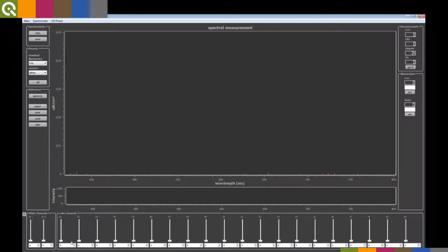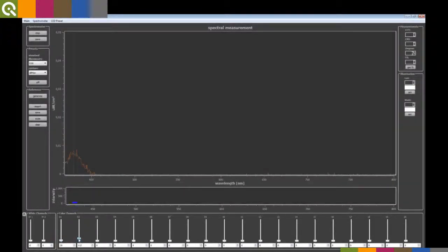One way to get the Cal1 producing a spectrum is to use the sliders in the LED control area. Each of the 22 LED channels can be adjusted in 1,000 steps by pushing the slider, scrolling the mouse wheel over a slider, or typing in a new value. As you can see, a gray helpline appears in the measure window when clicking on a channel slider.